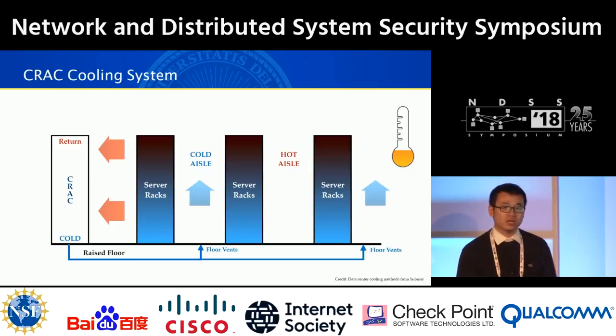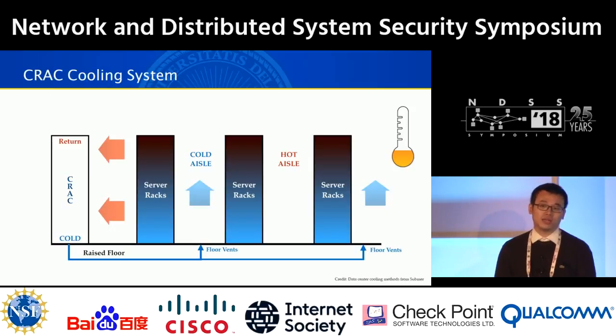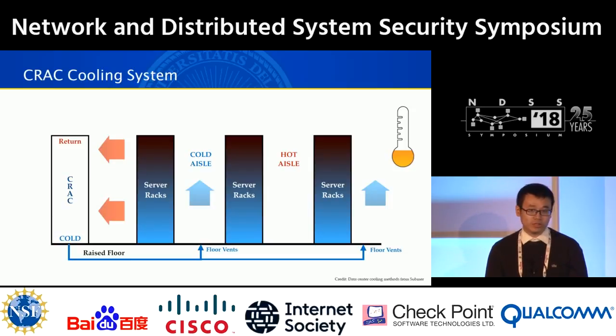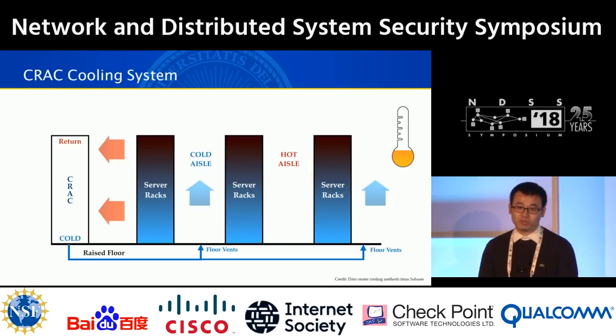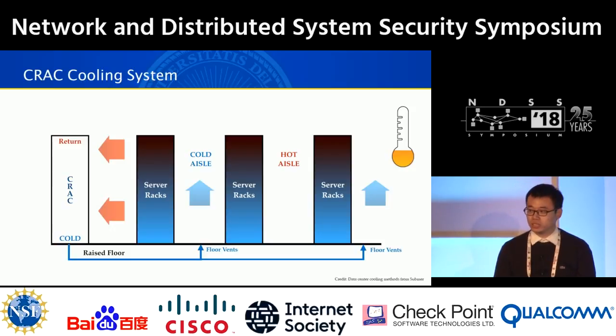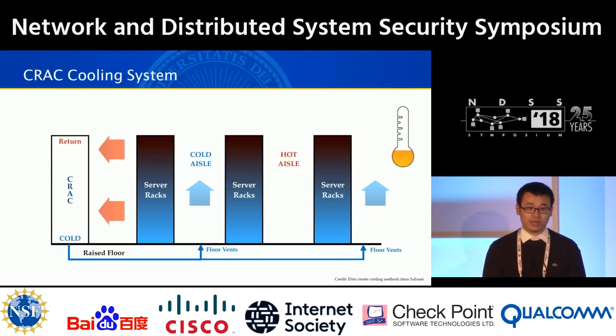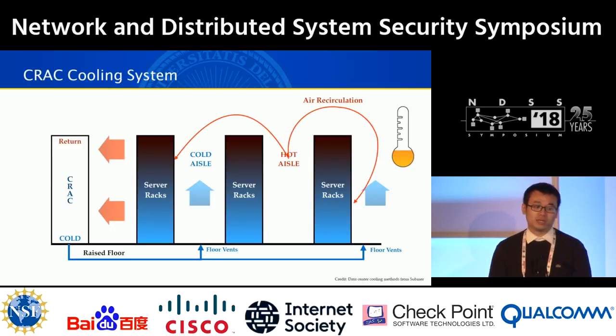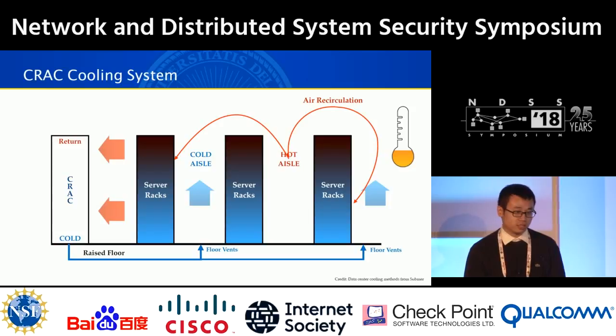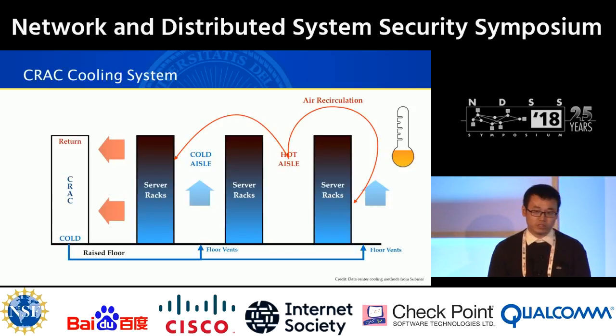Ideally, the cold air and hot air should be perfectly isolated for high cooling efficiency. However, gaps exist between the insulation material and the server racks. As a result, the hot air generated by one server might enter the cold areas and affect the inlet temperature of other servers, causing air recirculation.